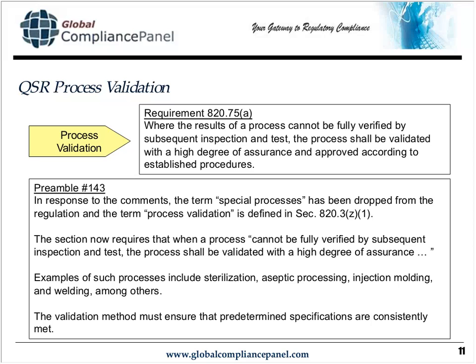What they're saying is that when a process cannot be fully verified by subsequent inspection and test—in other words, you can't check everything that comes out of the process—then you have to validate it with a high degree of assurance. They give some examples: sterilization, aseptic processing, injection molding, welding, and so on.